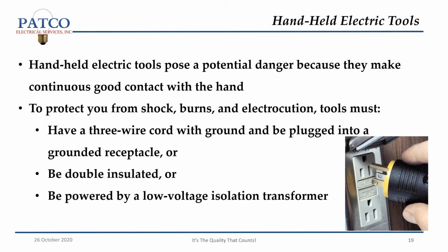Handheld electric tools. Handheld electric tools pose a potential danger because they make continuous good contact with your hand. To protect you from shock, burns, and electrocution, tools must have a 3-wire cord with ground and be plugged into a grounded receptacle, or be double insulated, or be powered by a low voltage isolation transformer.